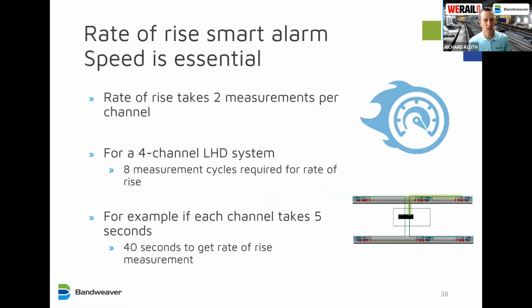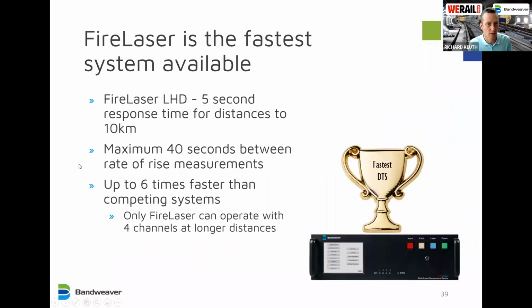So if we look at the maths behind that, rate of rise takes 2 measurements per channel. So for a 4-channel system, that means 8 measurement cycles to get a single rate of rise measurement across the whole tunnel. If we say we take 5 seconds per measurement, which is a typical time for the FireLaser, that means it takes 40 seconds to get a rate of rise measurement across all the tunnels, which, in the context of a tunnel, is a reasonable time frame, but you certainly wouldn't want to make it much longer than that. And the approvals dictate that you have to do it in about that time frame.